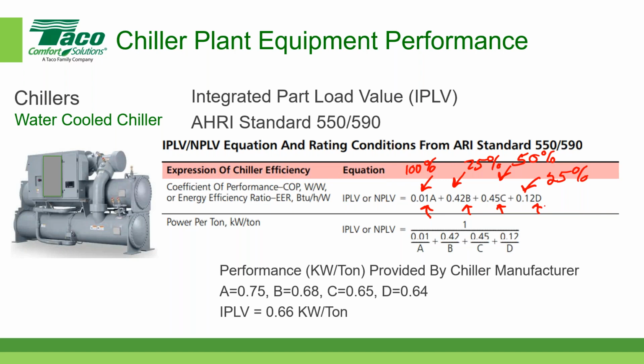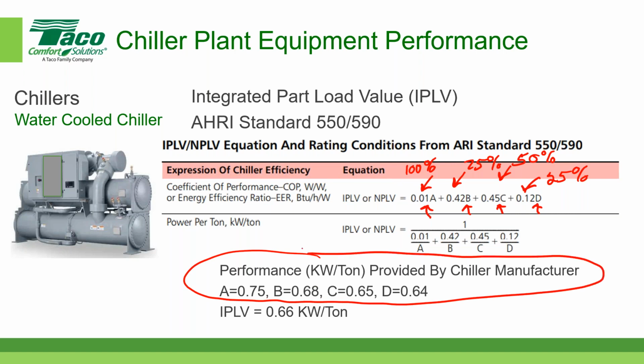and D values here? And so here are some numbers provided by a chiller manufacturer for those values. The A value is 0.75 kW per ton, 0.68 kW, 0.65, 0.64. And if we plug all of those numbers into the equation, the IPLV is 0.66 kW per ton. And chiller manufacturers use this value to compare the operating characteristics of one chiller versus another chiller.